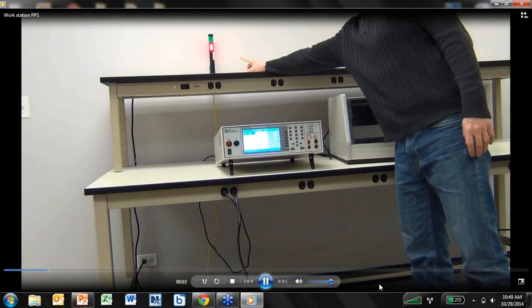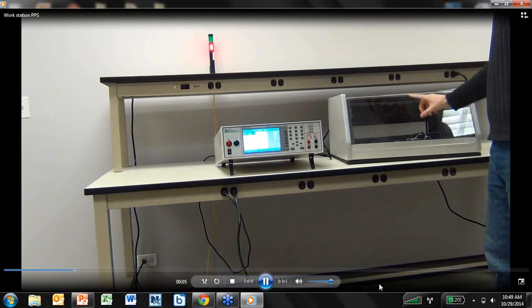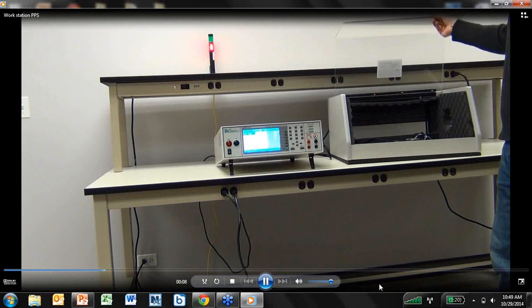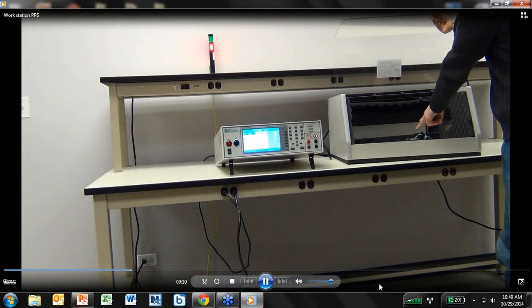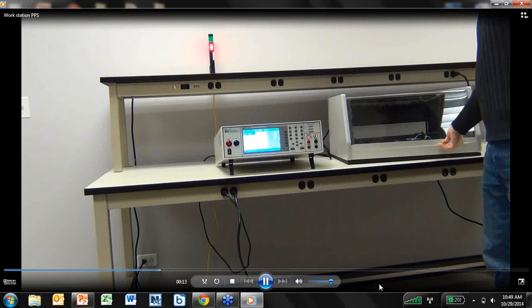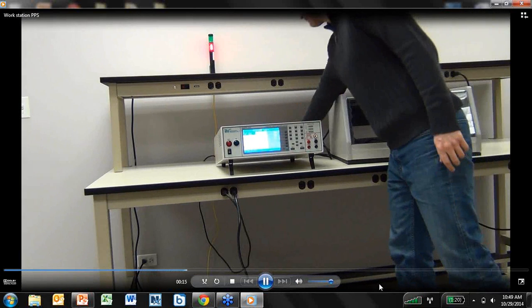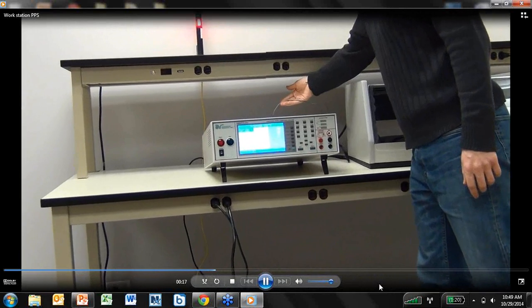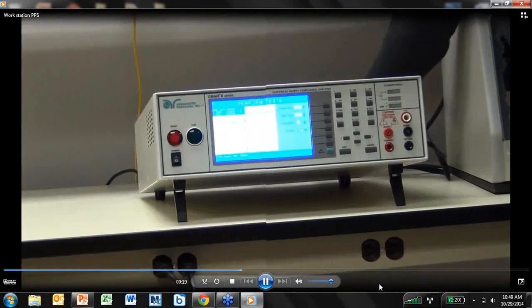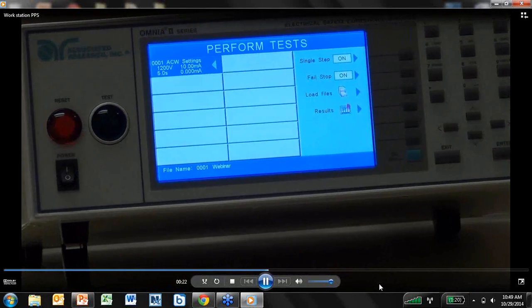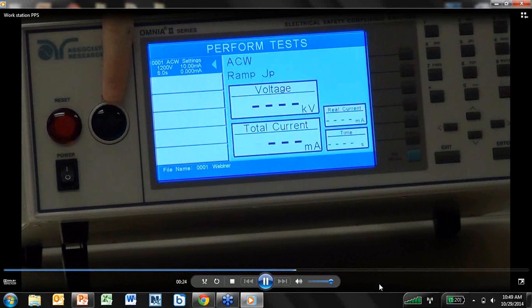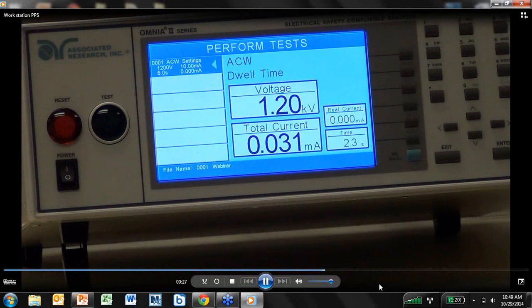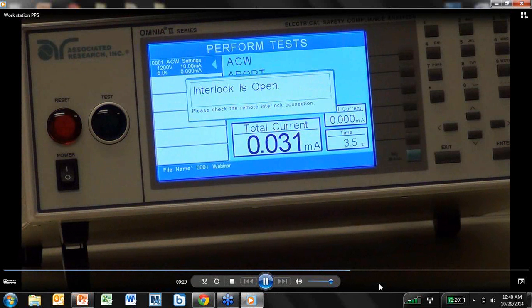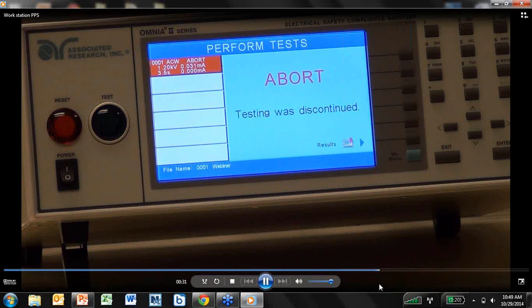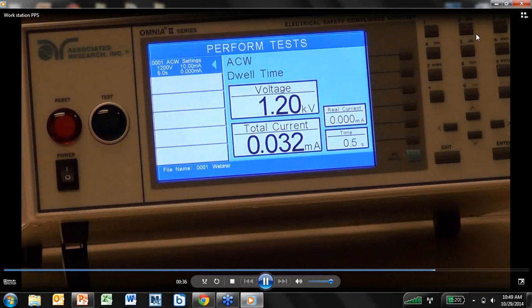What I'm showing you here, you can see I have a signal light that's illuminated red because I'm ready to go with this test. I have a DUT enclosure, so if I open the door you can see my test device in there, and I have an Omnia unit. That enclosure door is actually wired directly to the Omnia, to our interlock. So I'll start my test, and then I'm going to open the door. As soon as I open the door, you see it says interlock is open, and the test stops. That's the idea—we don't want it to go any farther than that.